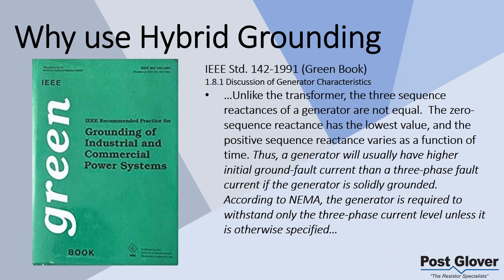So just to be specific, this is really a medium voltage generator application. We're not really talking about many other applications; I can't think of another one to use this on. So if you don't deal with medium voltage generators, you're probably not going to see this very often. But generally speaking, and to start, IEEE recommends that if you have a medium voltage generator, you want to impedance ground it, okay? That would mean reactance grounding or resistance grounding.